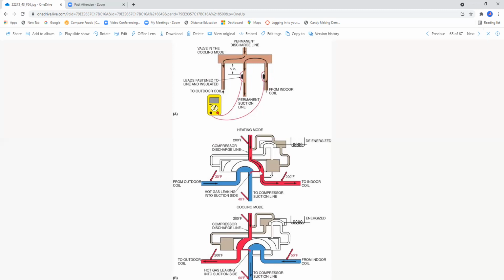Okay. Now, one thing I have not called your attention to, and this diagram makes it very clear, the center port is always called the permanent suction line. The middle port on the other side of the four-way valve is the permanent discharge line.